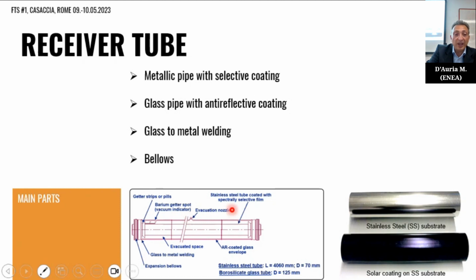Then we have a pipe in borosilicate glass with a film to reduce the reflection losses in the glass, increasing the optical efficiency of the tube receiver. The glass cover is connected to the steel pipe using metallic expansion bellows to compensate for the different linear thermal expansion of the glass and steel when the solar receiver is working at nominal temperature.